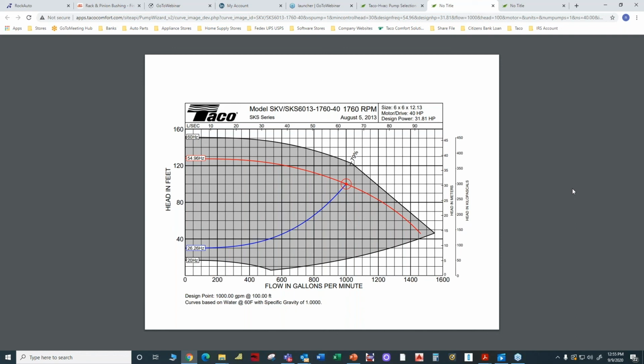And then for minimum flow, let's assume in this case you had 150 gallons per minute, then again you put it at a constant flow of 150 gallons per minute. It finds the actual pressure drop with all the valves closed with the exception of the three-way valves. And it'll find the actual pressure drop, in which case you can adjust the control head and you can adjust the design operating point, and you'll get a curve. I'm going to grossly draw one in here. You'll get a curve perhaps that starts here, and it's parallel with the other curve.